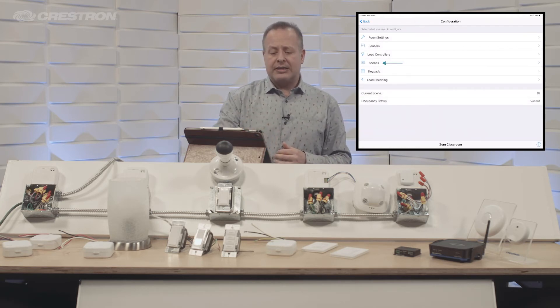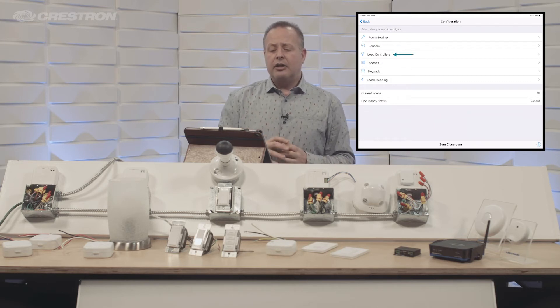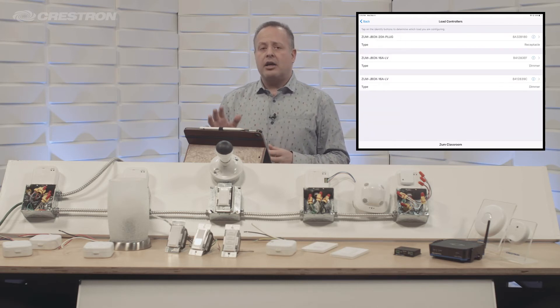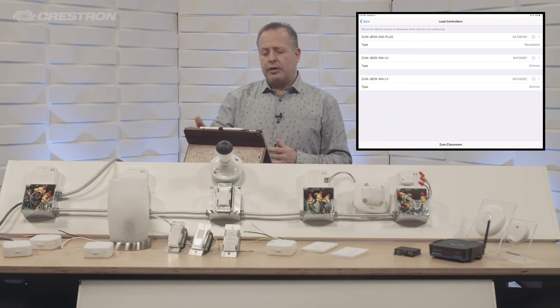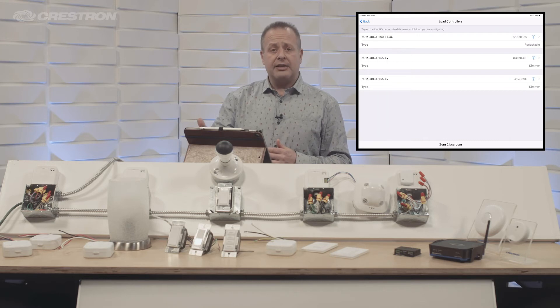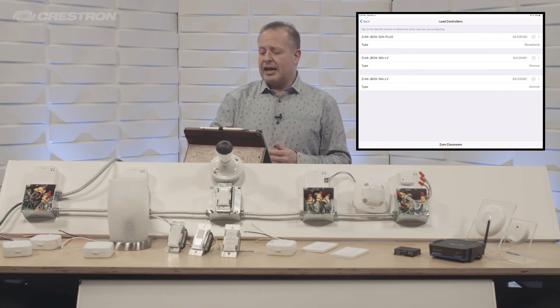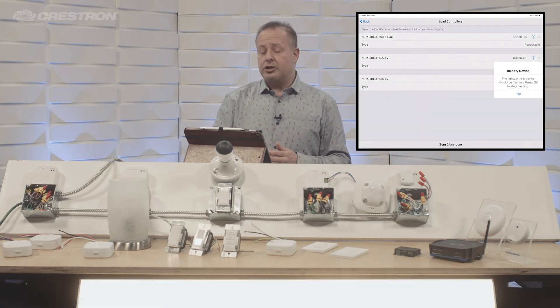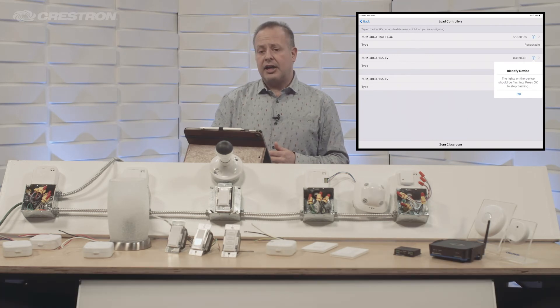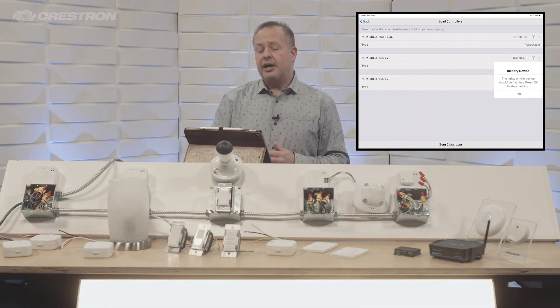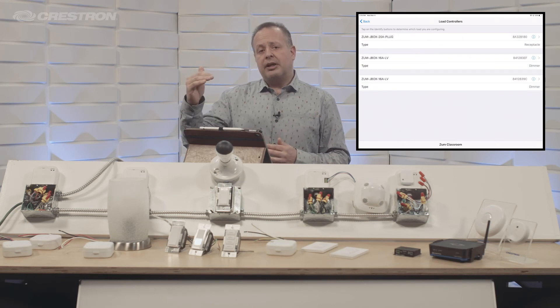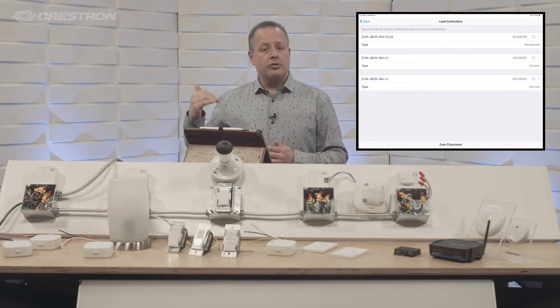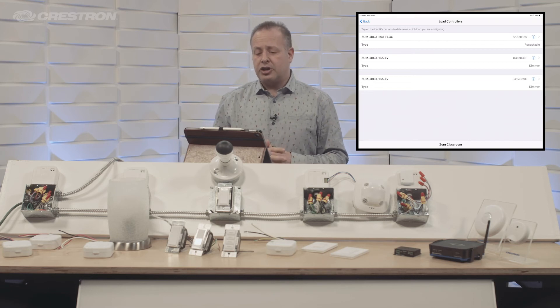You can also set scenes, adjust sensors, and even go as far as identifying load controllers within the space. What you see right now is multiple low voltage, or LV 0-to-10, devices. You can identify those low voltage or LV devices by clicking on the identification button, and it'll flash that particular zone. It gives you the ability to assign zone 1, zone 2, zone 3, and so on within your job site.